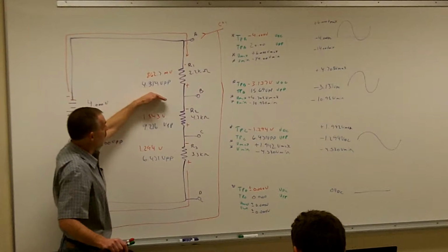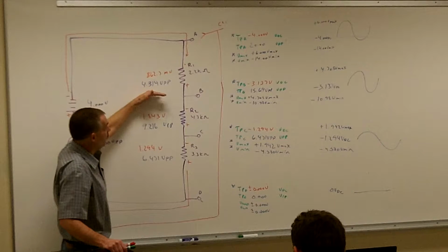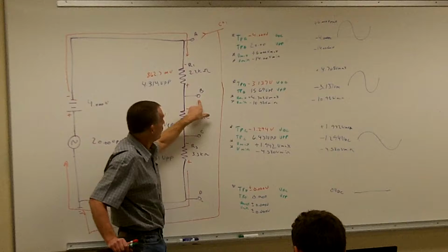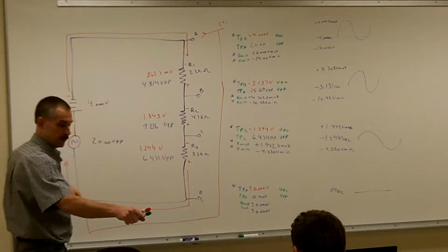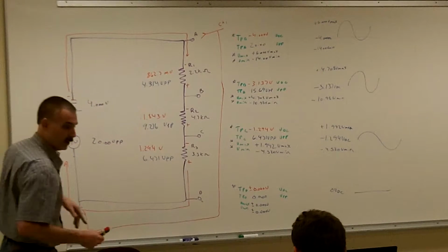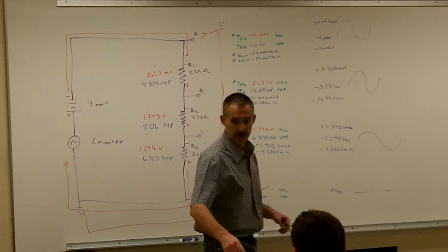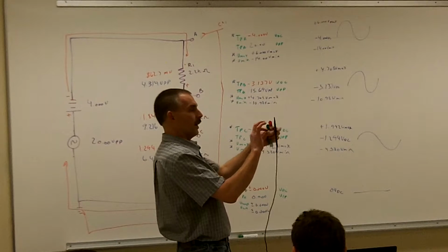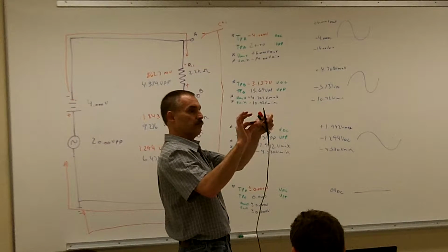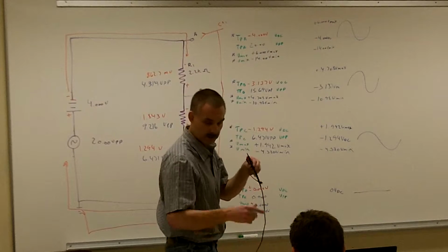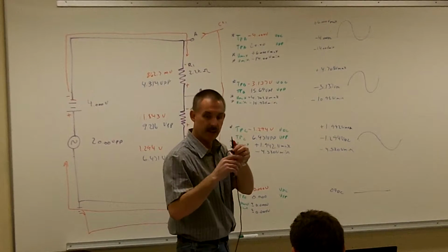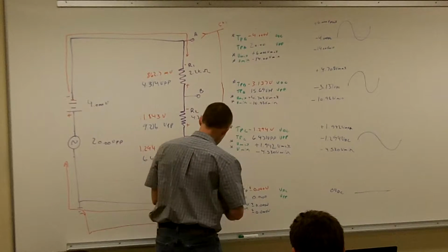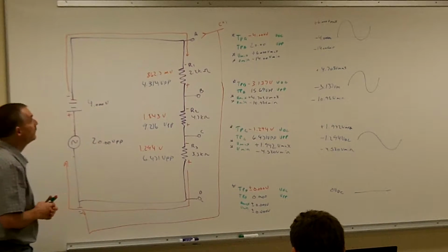If we're working with something with high voltage and high current capabilities, and we float that ground, that current is physically going right through the oscilloscope and then right back into the earth ground. So if we're measuring something with very high voltage and a lot of current capability, the ground wire will actually burn right off, or your oscilloscope is going to burn up. So you're going to have to be very careful about floating the grounds when you're out in the industry. That's all right. Oscilloscopes are really cheap.